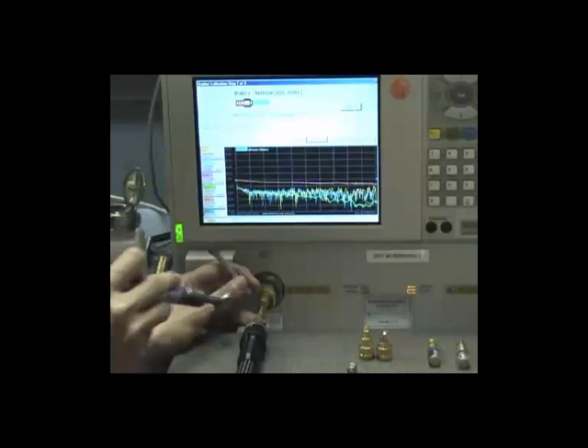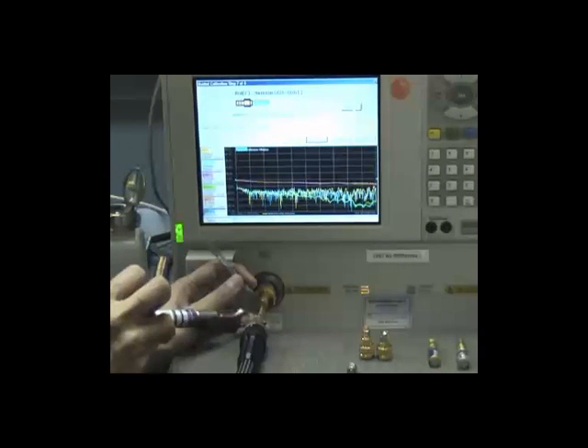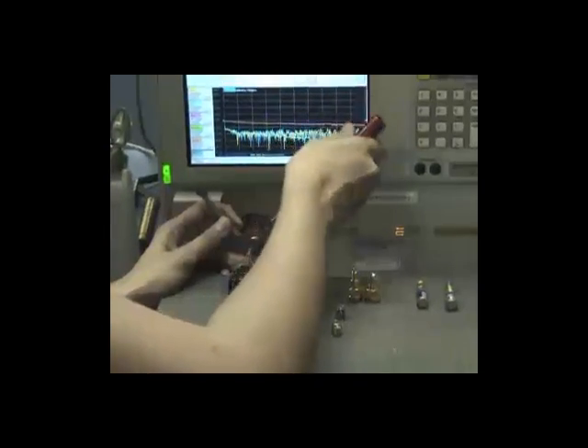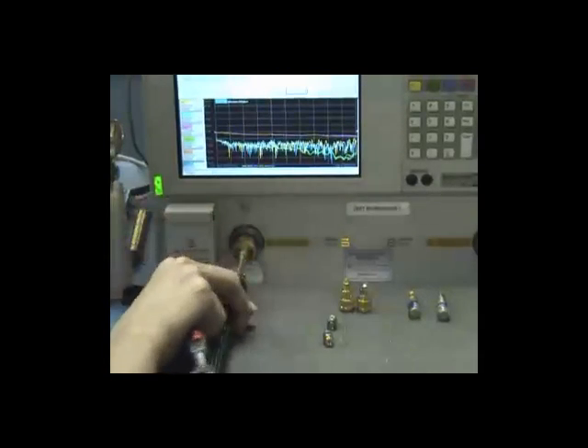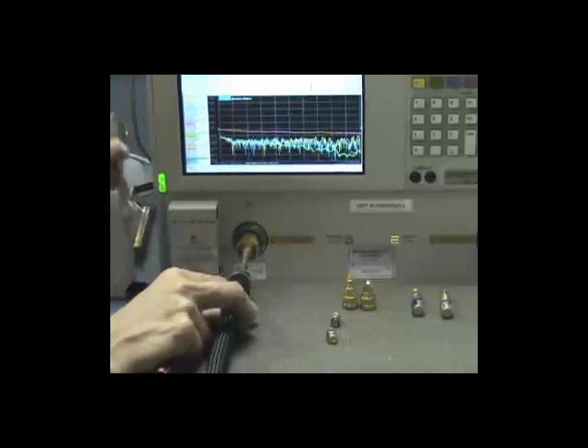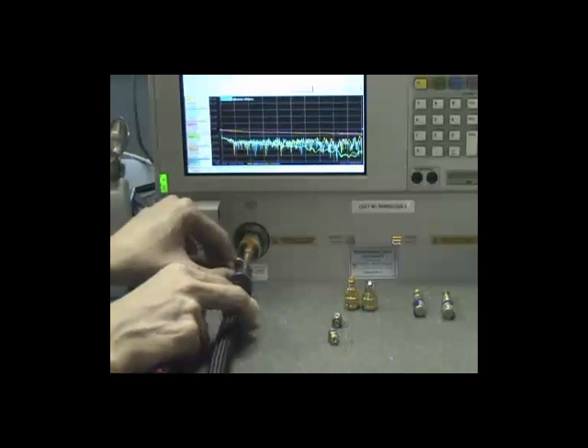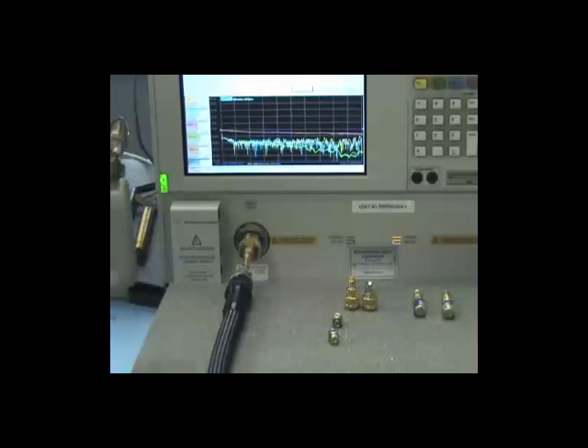As you can see, this is a longer airline, so when I'm making that connection I am trying to support the other end with my finger here because the weight of it would surely be too much for that really thin airline. Just make sure you are supporting both ends of the airline as you're making the connection or as you're torquing the body.